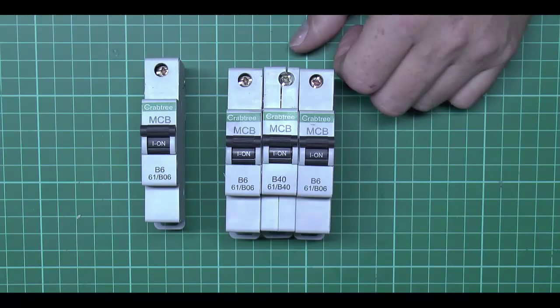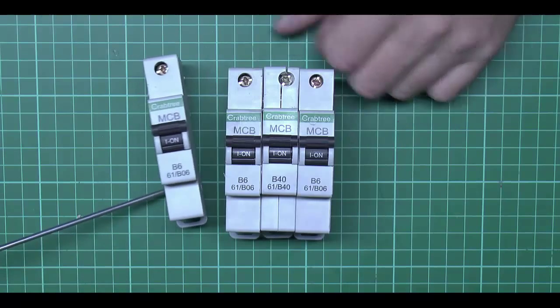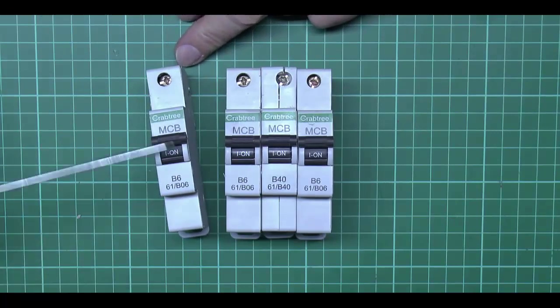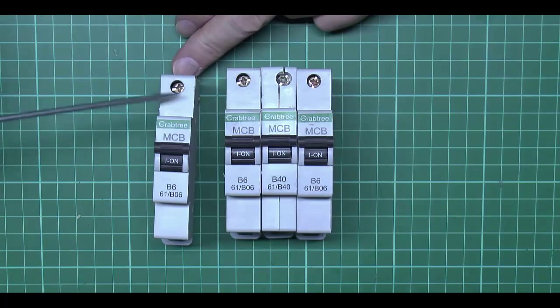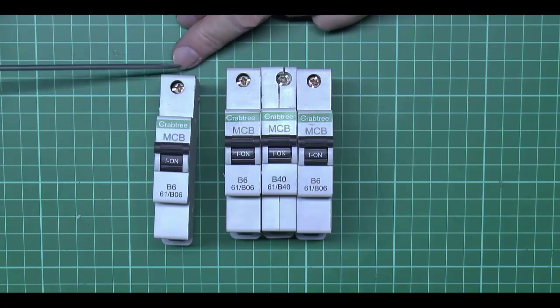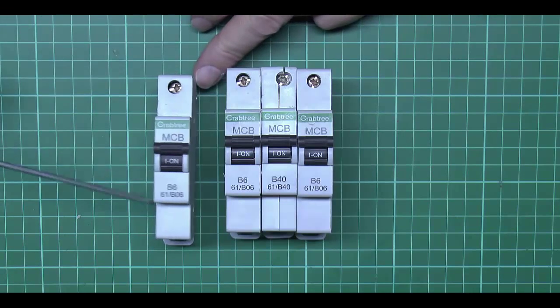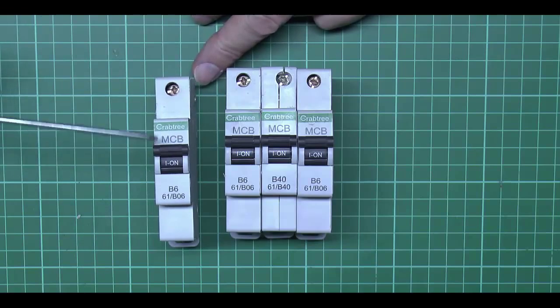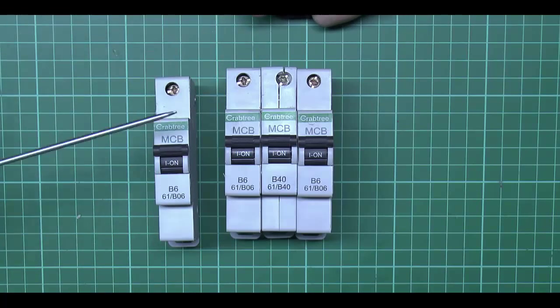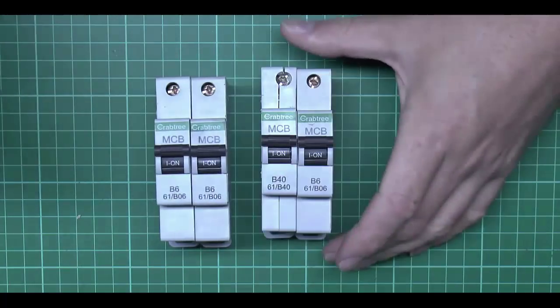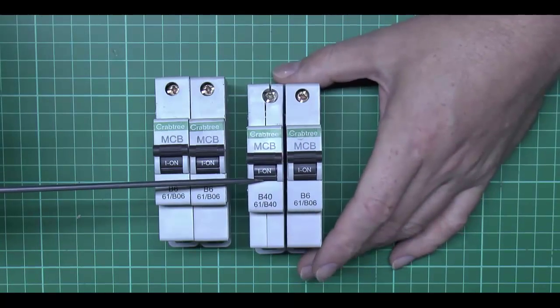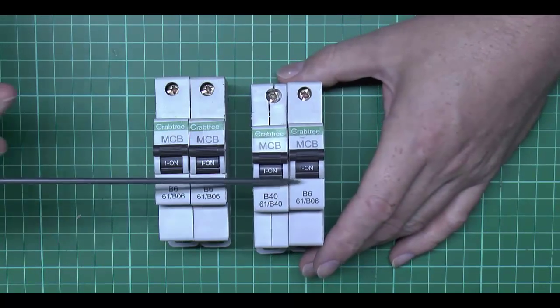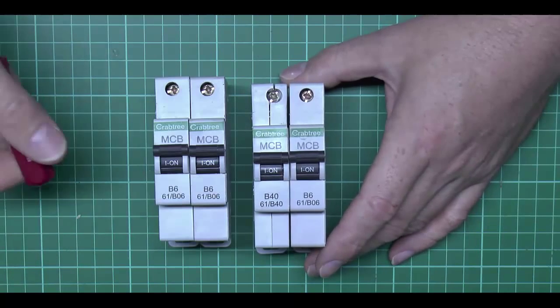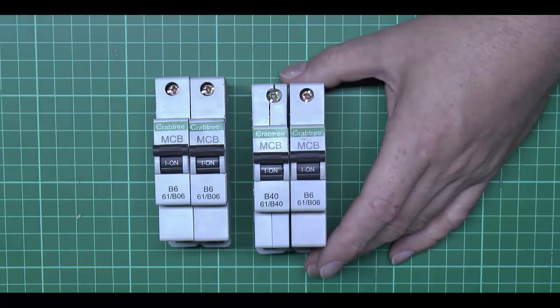The power will be connected in at the bottom, so you'll normally fire a screw there, or in the case of this one, the tab on the back, through the mechanism inside, and then your outgoing circuit will be connected at the top here. And this particular one is a 6 amp device, so typically that would be used for a lighting circuit. And there's another 6 amp one here. This 40 amp one was actually for a cooker circuit, and then there's another 6 amp one over there, which again was for another lighting circuit.